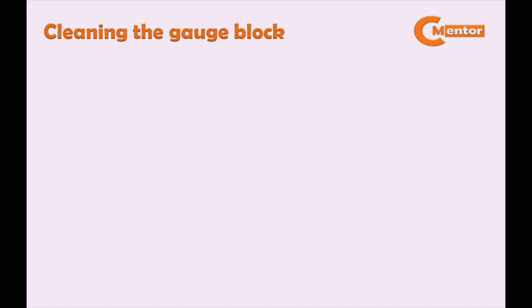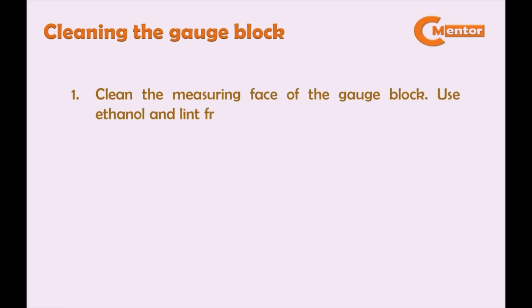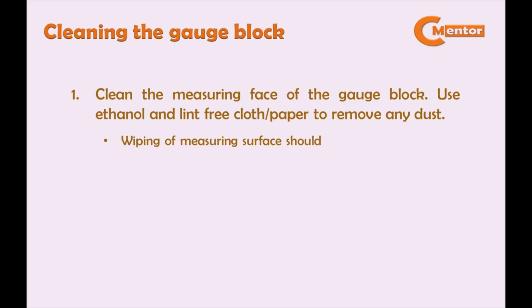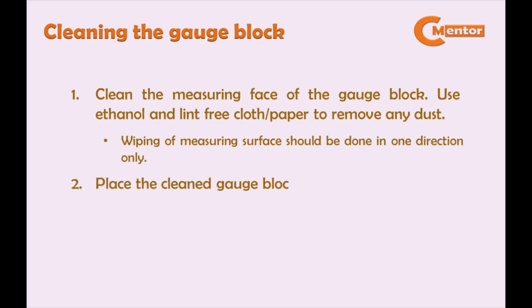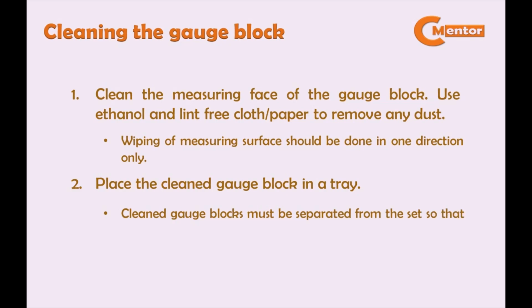Before calibrating, we need to clean the measuring face of the gauge block. Use ethanol and lint-free cloth or paper to remove any dust. Wiping of the measuring surface should be done in one direction only. Next, place the clean gauge block in a tray. Clean gauge blocks must be separated from the set so that they will not mix up with the unclean gauge blocks. The next video is the actual cleaning of the gauge block.